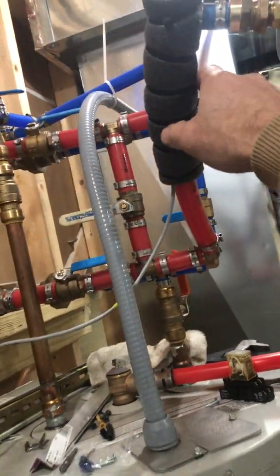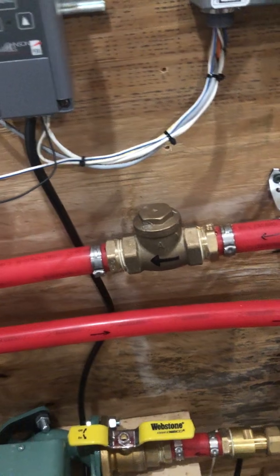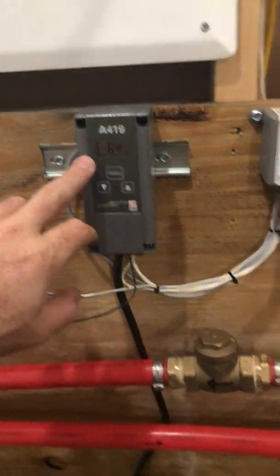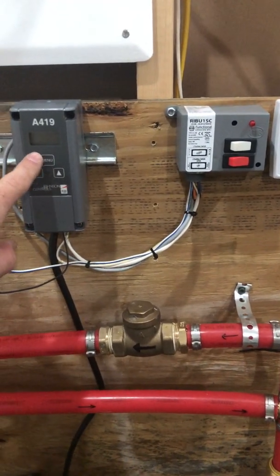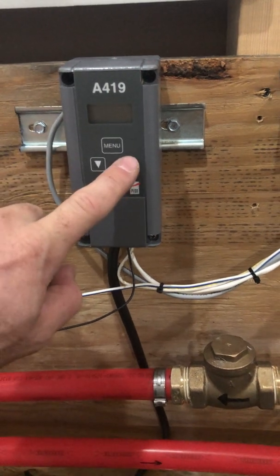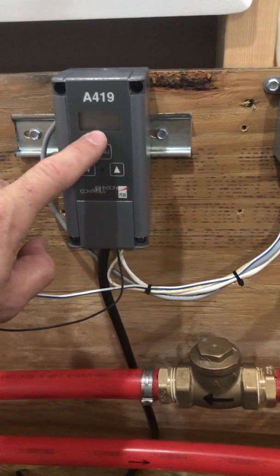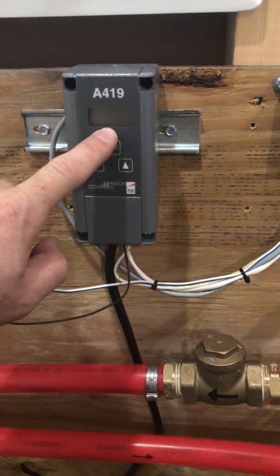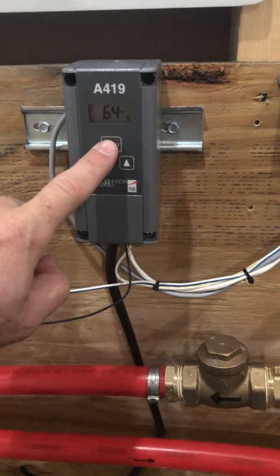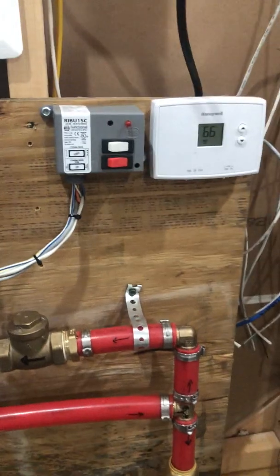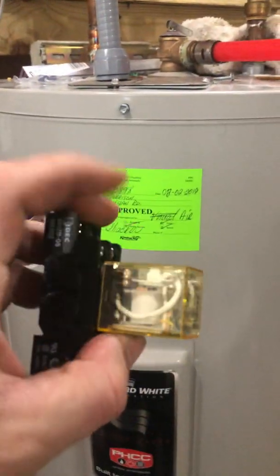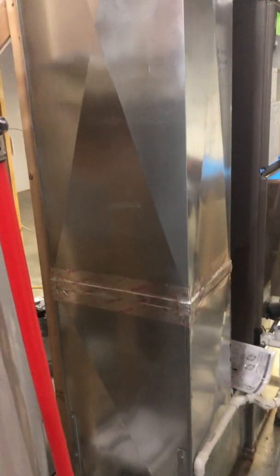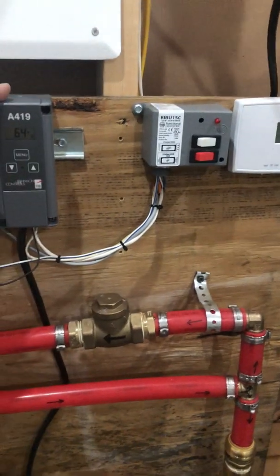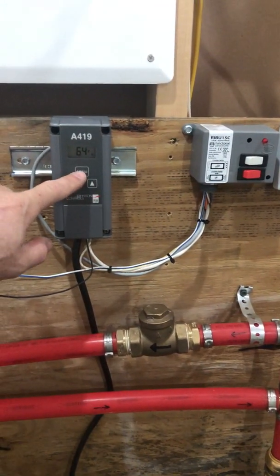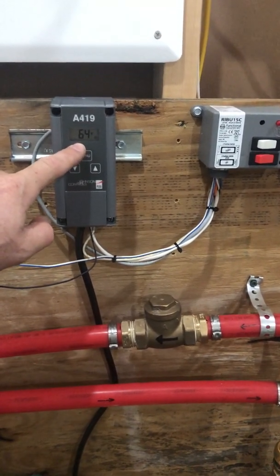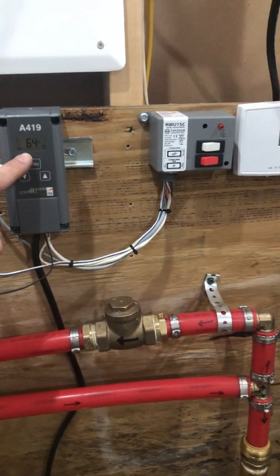So this is measuring the water as it comes in the house. So as the water is flowing through the system, what this controller does is, and I'll show you where it says, this is SP, set point. So my set point is, that's actually a differential. So my set point's 100. So if my water temperature in the boiler is at 100 degrees or more, this controller is actually controlling a couple of these relays inside the air handler. So what it'll do is it will not allow my heat pump to function when the thermostat upstairs calls for heat. If I have 100-degree water temperature or more, it won't let my heat pump kick on. It will only operate the fan.